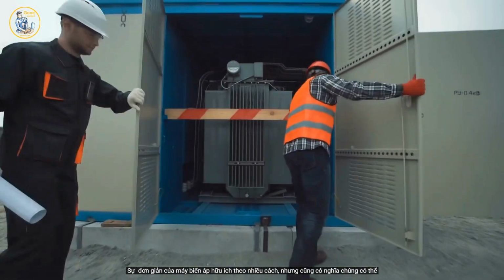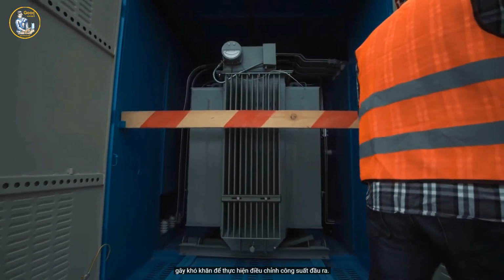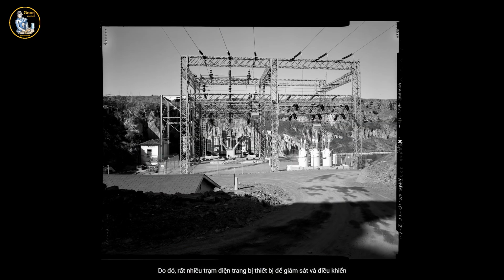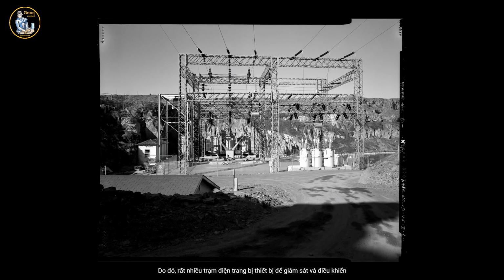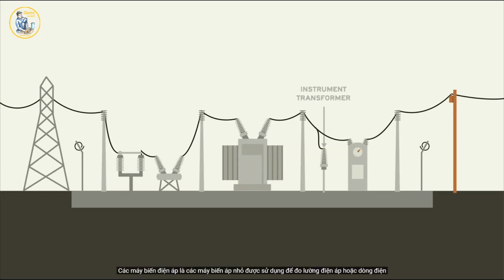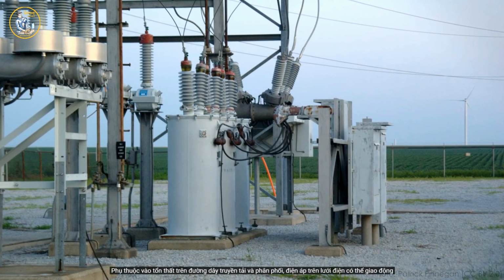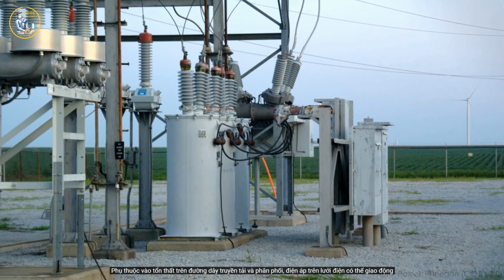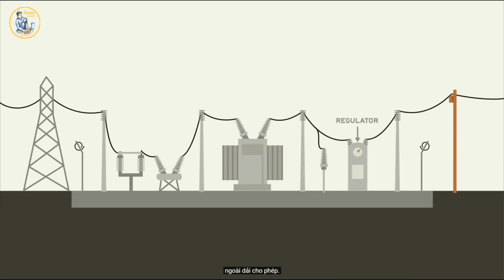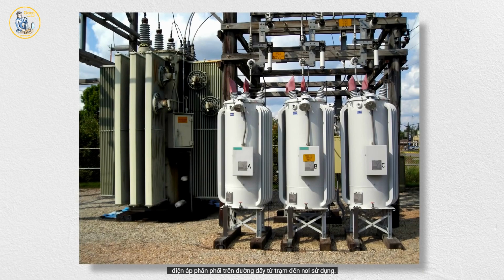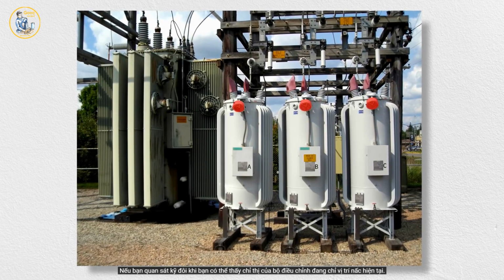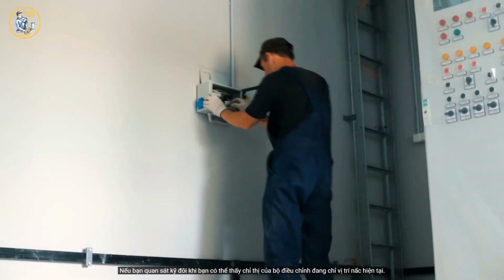The simplicity of transformers is great in a lot of ways, but it also means it can be difficult to make fine adjustments to the power leaving the substation. Because of this, many substations include equipment for monitoring and controlling the power on the grid. Instrument transformers are small transformers used to measure the voltage or current on the grid or provide power to system monitoring devices. Depending on the varying transmission and distribution losses, the voltage on the grid can also swing outside an acceptable range. Regulators are devices with multiple taps that can make small adjustments up or down to the distribution voltage on feeder lines leaving the substation toward customers. If you look closely, you can sometimes see the regulator dial indicating the tap position.